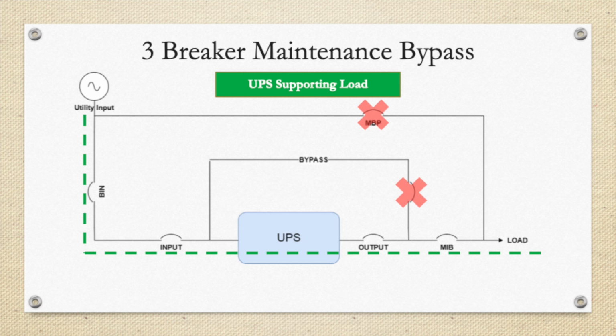If we want to get over to the maintenance bypass and off the UPS system, it is imperative that we transfer the UPS to internal bypass before we go over to maintenance bypass. The reason for this is, if we were to close MBP right now under this configuration, Ohm's law says power is going to go to the path of least resistance. That means when we close MBP, that utility is going to look 2 places, out to the load or back into the UPS. Unfortunately, most UPSs have a very low output impedance, and chances are that utility power is going to backfeed the UPS and is going to do significant damage to the UPS, and quite honestly will probably trip the feeder breaker to the system, and there will be a loss of critical load.